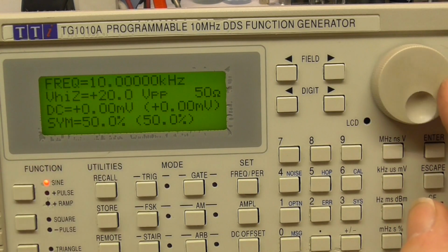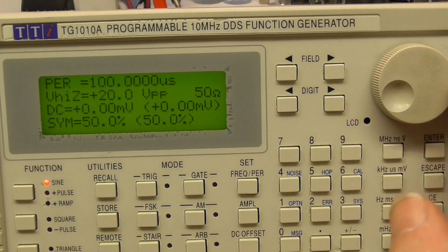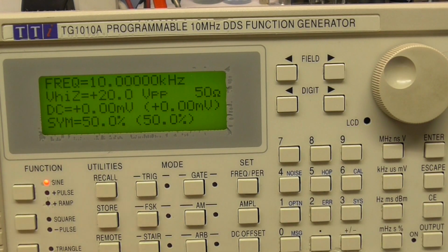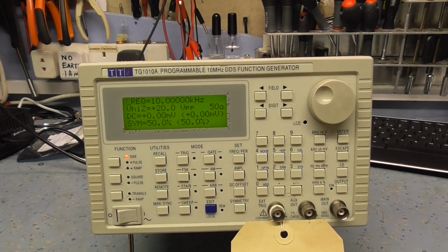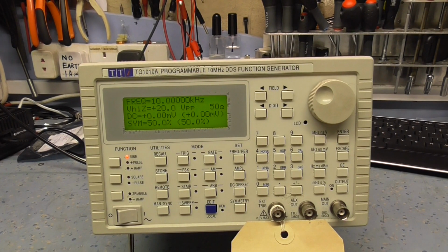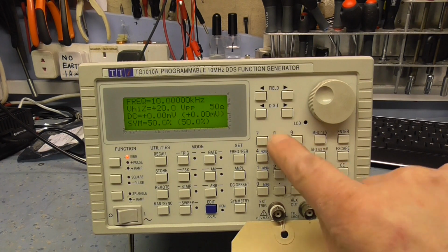So that suggests there's no processor error. There is a problem with one of these switches here. And I think it's exactly the same as the Rohde & Schwarz. One of these switches is short, or there's a break in the board maybe, and that's why we've got no control over the front panel. So I'm going to have to take the front off, pull it all apart, and have a look inside, see what type of switches it's got. It's probably these membrane switches, but I can hear them clicking nicely.